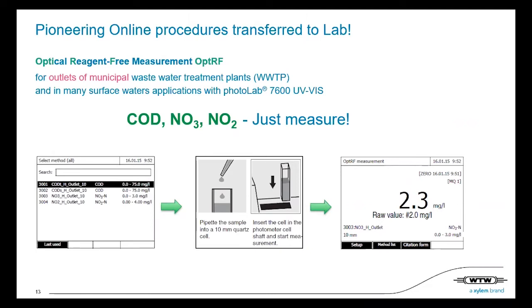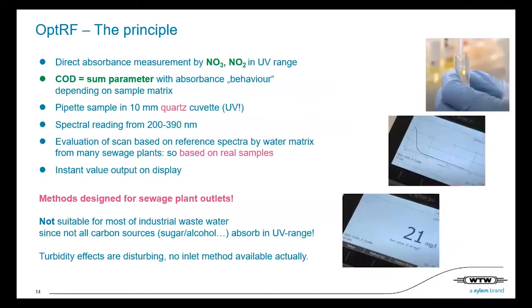So how is this possible? I want to give a short overview of the principle of this measurement. In comparison to a reagent determination, we are measuring the absorbance directly in the UV range. You know that for nitrite and nitrate anyway, it's around 220 nanometers in some countries, some standard methods. But here we have a complete scan and an algorithm behind it.